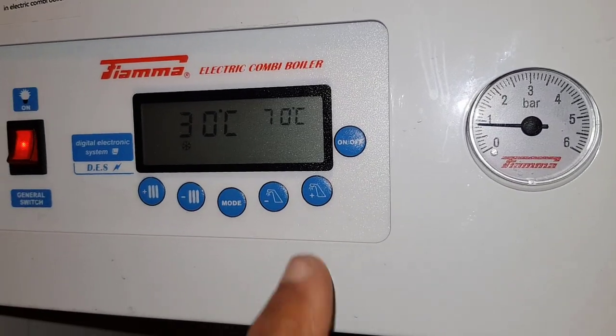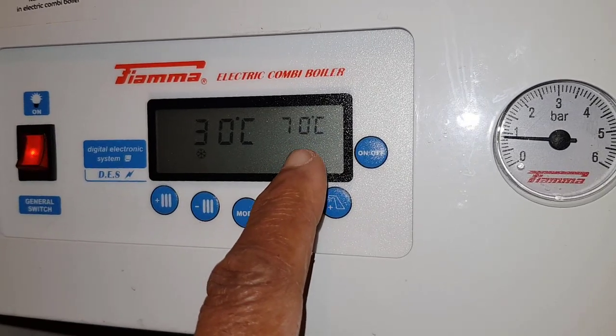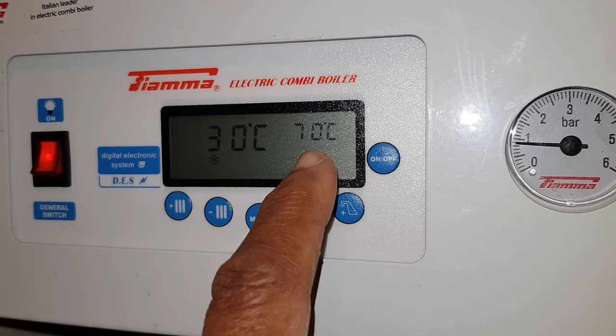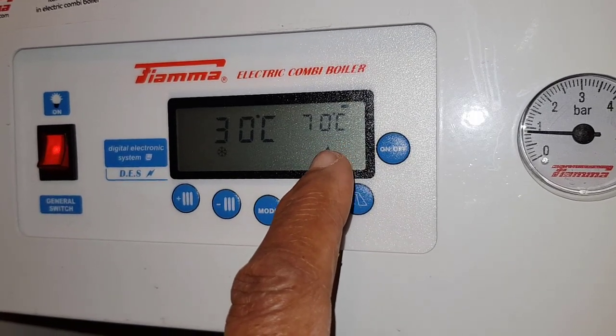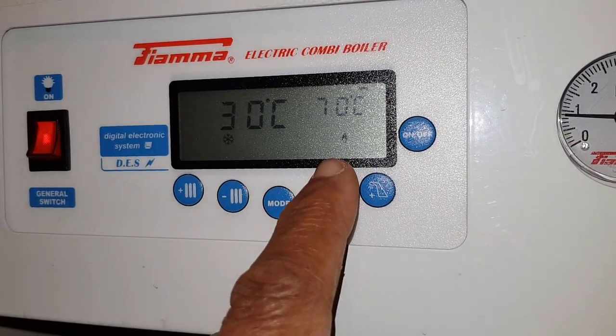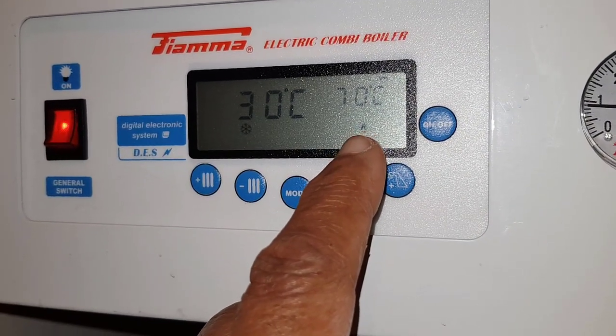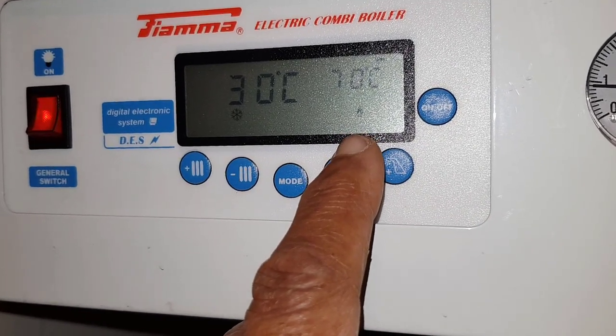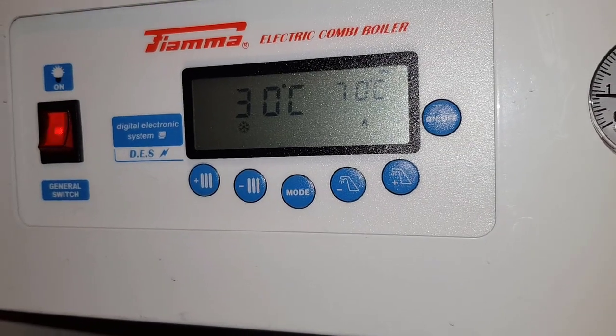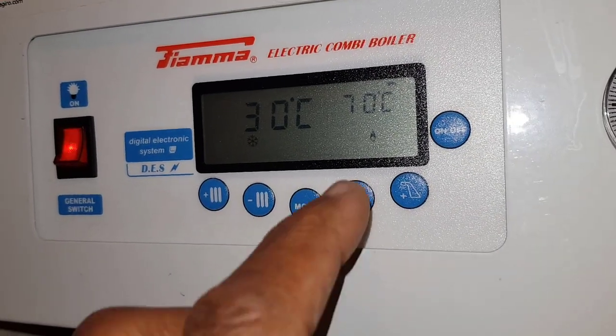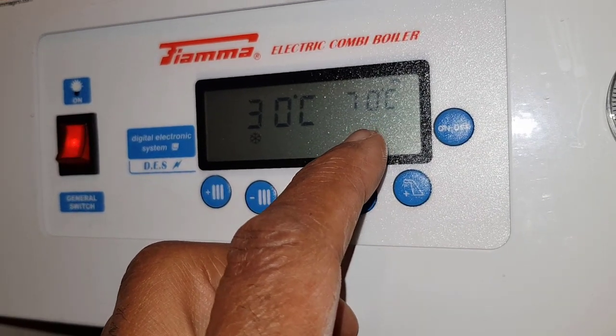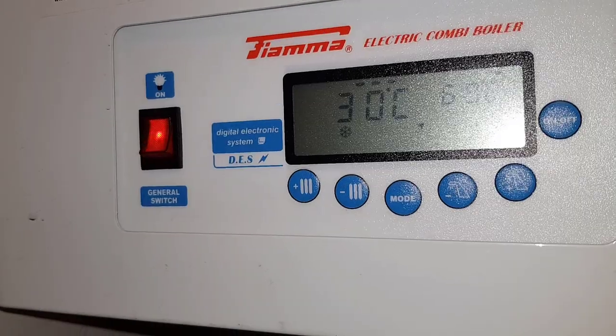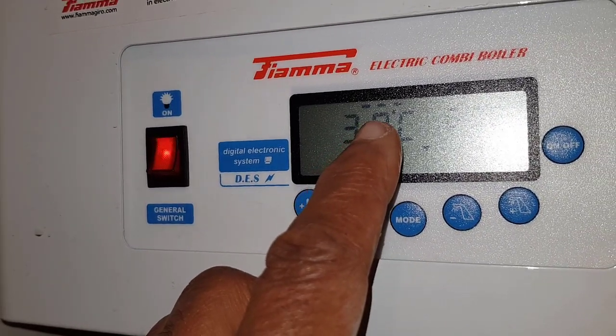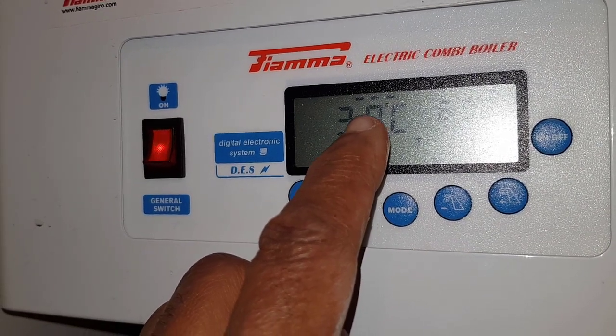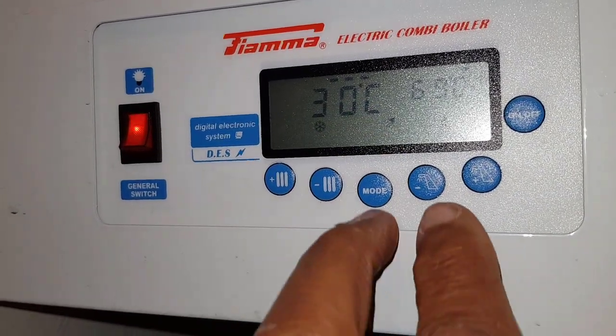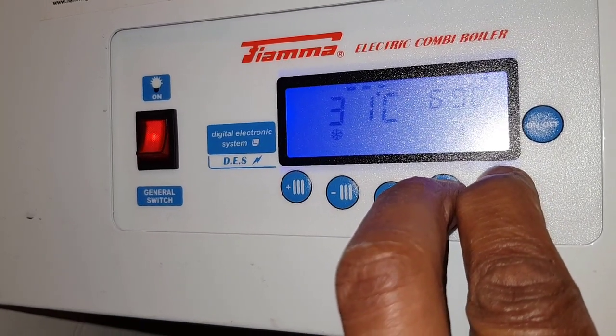Now what's happening, this 70 degree temperature here is from the hot water unvented cylinder, which I'll show inside the boiler in a minute. This is the 2 kilowatt immersion heater, which is connected to that unvented cylinder. It's trying to heat it up, but it won't keep it maintained. This will start dropping in temperature soon, which it's just dropped now. This represents the main heat exchanger coming on, but we still should have got that other tap symbol.